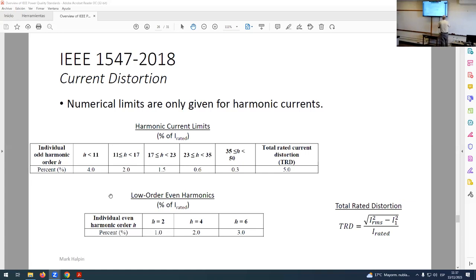Okay? Well, so what we've come up with is this concept of total distortion. And the total distortion is based on the difference between the RMS value of the current and the power frequency term. Okay? Whatever that difference is, represents the distortion at whatever frequency or frequencies it may occur. So that's a significant difference in the newer IEEE power quality documents as far as harmonics are concerned. And it got started with 1547.